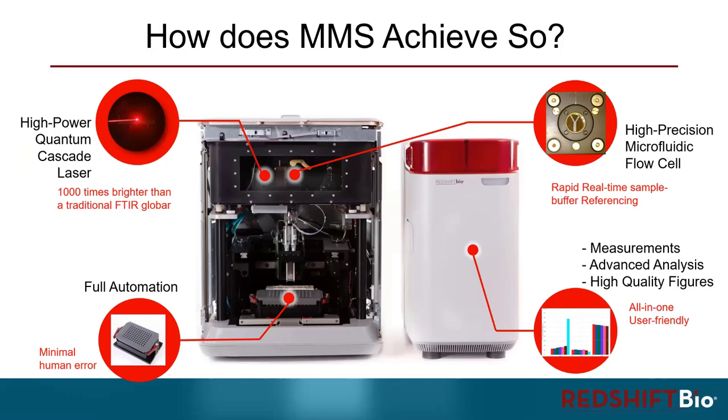So how does MMS achieve so? Let's take a deeper look into it. First, at the heart of MMS is the high power quantum cascade laser, which is 1000 times brighter than a traditional FTIR globar.